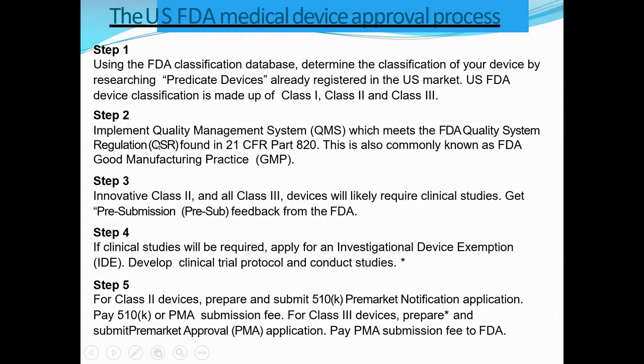The second step is to implement a quality management system. Like in the pharma industry, we call it GMP, good manufacturing practices. In medical devices, we call it a quality management system. So QMS is very, very important to implement in the medical device industry, which meets the FDA quality system regulation, also called QSR, as per 21 CFR Part 820. This Part 820 is very important when we talk about US FDA.